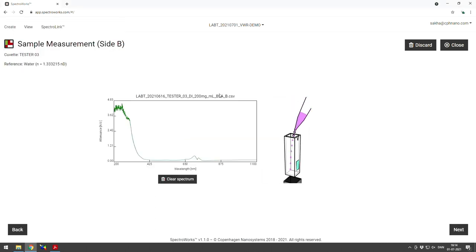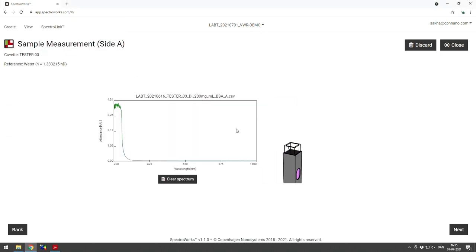Here you can see the spectrum with the data model. Just below the graph, the fit quality shows 88%, which is quite high, meaning the system is well calibrated and SpectroWorks understands all the variables in the optical measurement. We click next and are ready with the sample measurement. We upload the side B spectrum for 200 mg/mL BSA concentration data, click next, and then upload the side A spectrum. The side A spectrum is basically flat above 300 nm — normally there is no signal to give you concentration, but we use the side B spectrum to get the concentration.